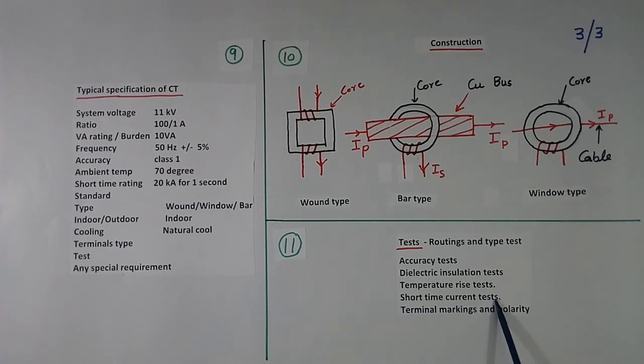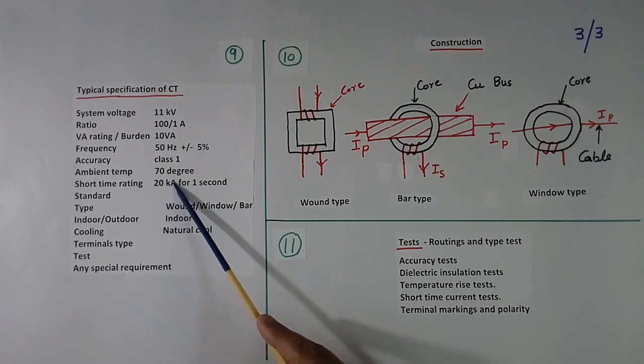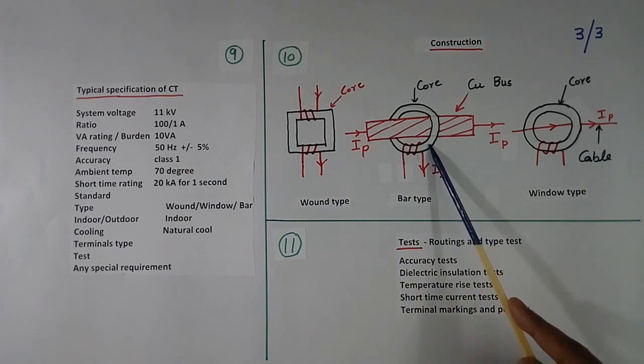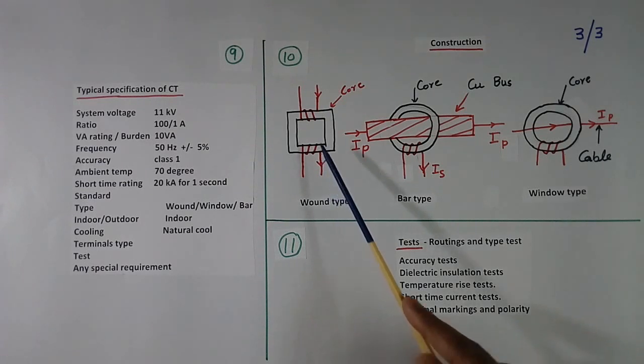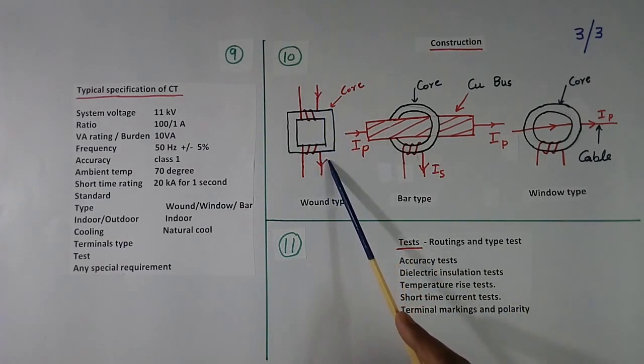Then short time current test. Here, suppose we write this. Then we have to give 20 kA in the primary for 1 second and see whether the CT is working or not, it is failing or not. Then terminal marking and polarity. Means it is marked properly. This is primary and this is secondary. This is terminal 1, this is terminal 2. Like that.